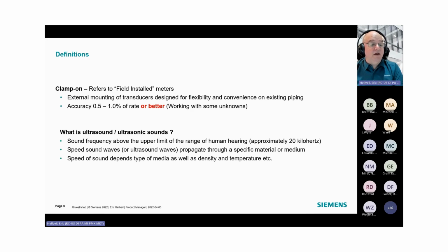Now, the clamp-on ultrasonic basically refers to field installed meters. So these are, as I mentioned, externally mounted transducers. A transducer both sends and listens for transmission signals, and we'll talk a lot more about that in a minute. But they're designed specifically for external mounting in the worst conditions, underwater, out in the desert, in the backyard, by the chemical plant, to be mounted on plastic pipes, to be mounted on metal pipes, whatever kind of pipes you have, even lined pipes, not a problem. They offer an accuracy from 0.5% to 1% of rate or better.